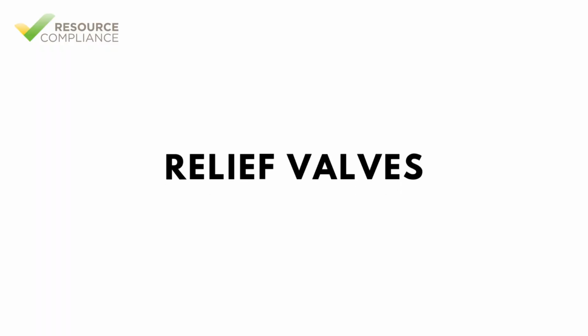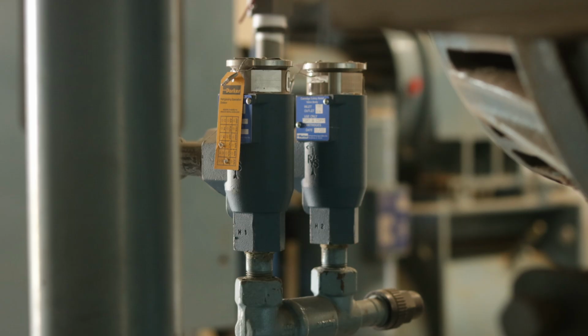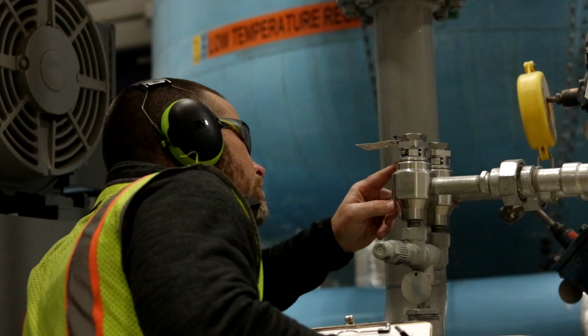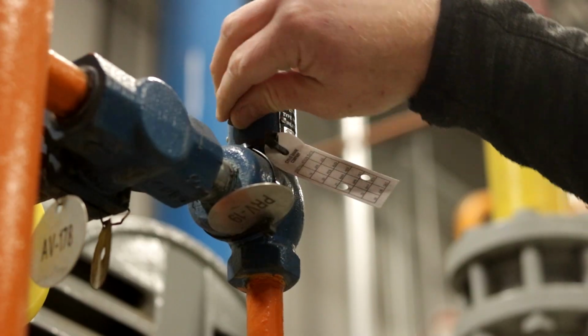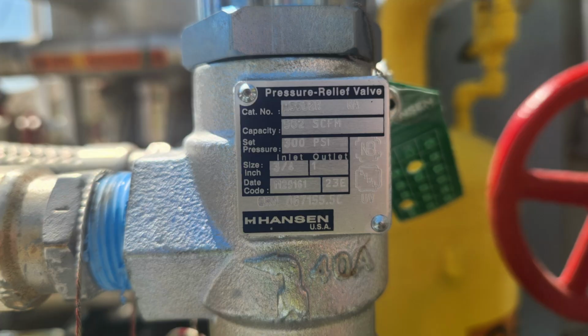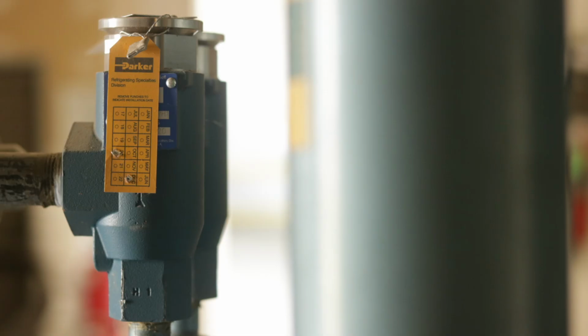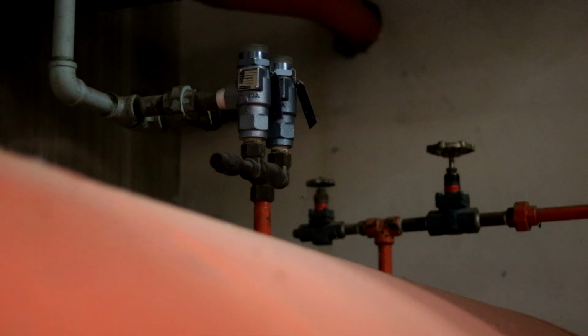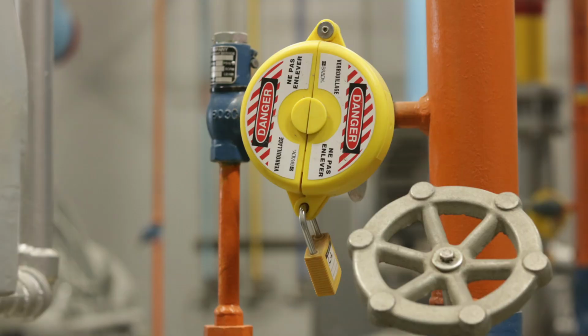Refrigeration relief valves should be inspected annually to verify that the relief valves have the correct set pressure and capacity, the ASME seal is unbroken, the relief valve has a legible nameplate, the installation date is within 5 years from the date of the inspection, no stop valve is installed upstream of the relief valve, and any stop valves installed downstream of the relief valve are locked open.